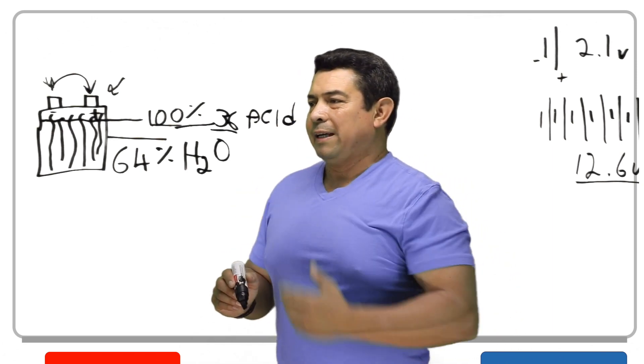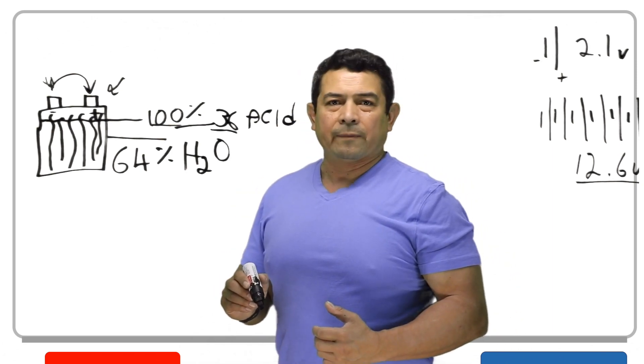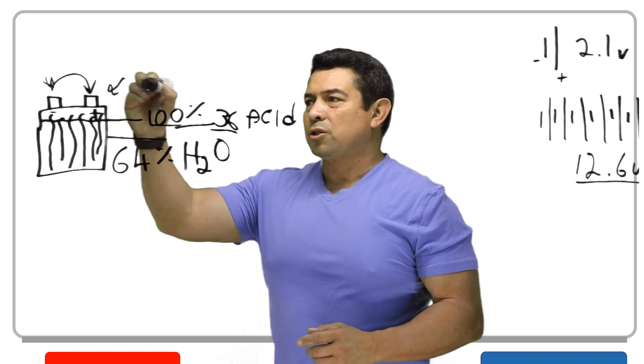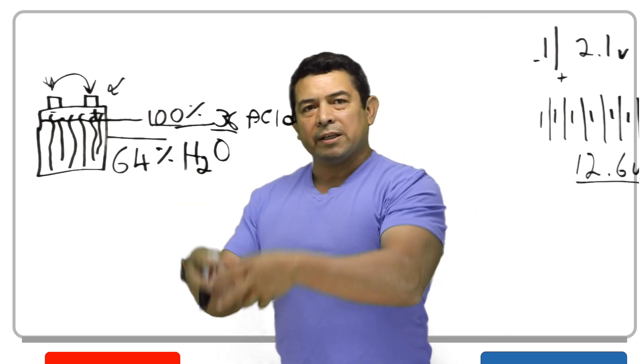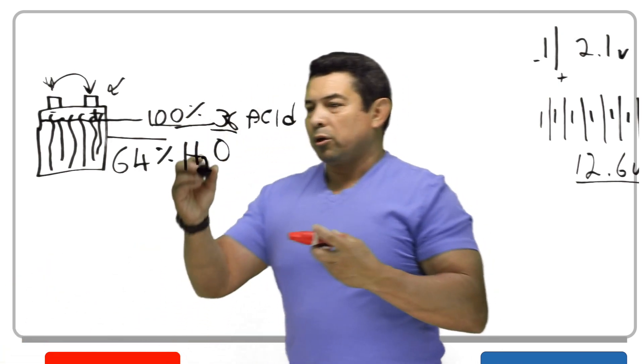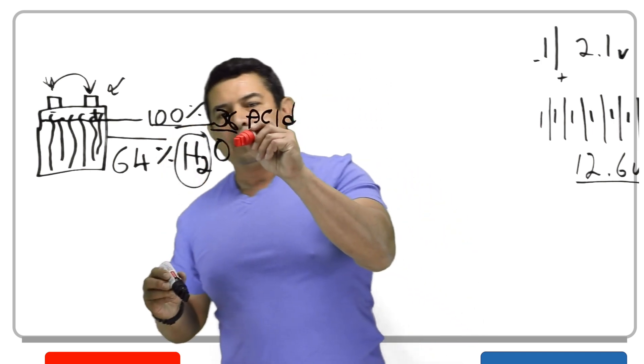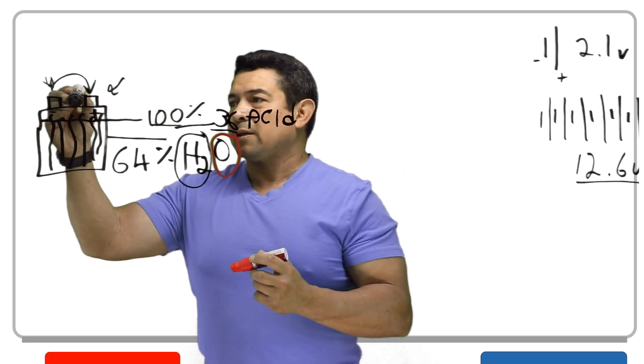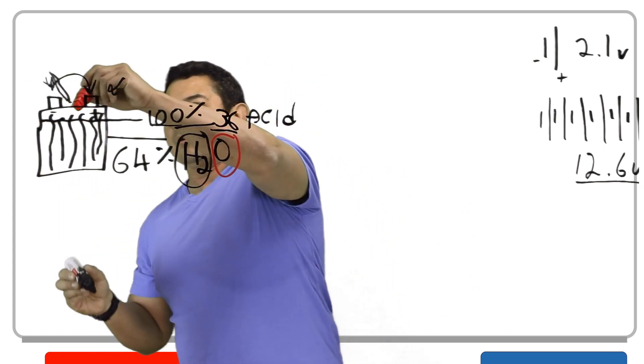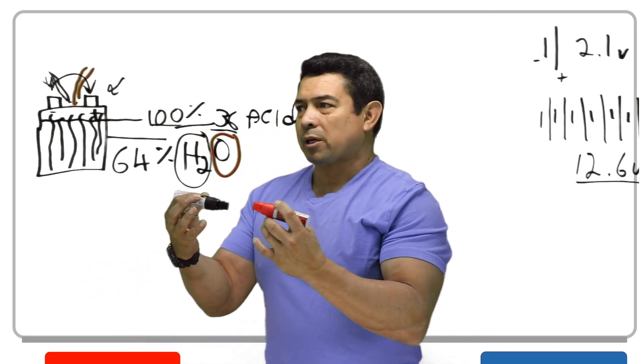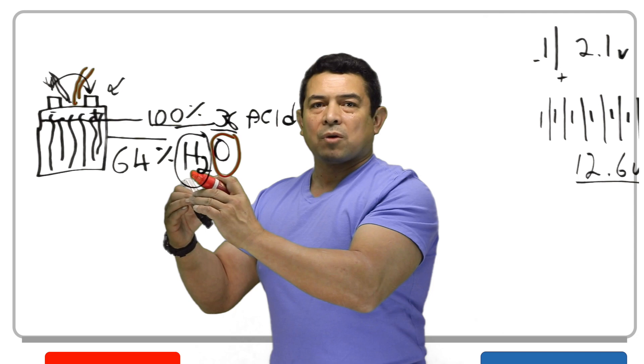At some point they tell you that you need to add water to the battery. Why? Because as we charge this battery, we're putting electricity into it, and when we do that we're going to break the H2O into hydrogen and oxygen. Because of that, we're going to get a little bit of hydrogen coming out and some oxygen coming out as we're breaking it apart. Eventually the level is going to drop.